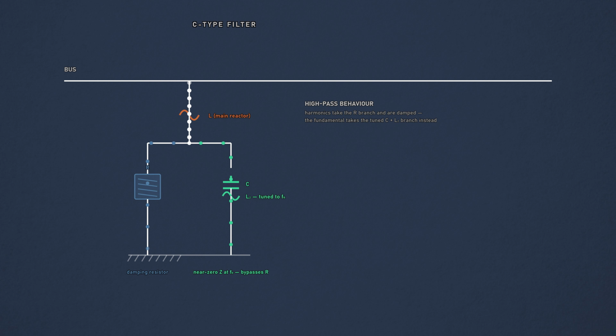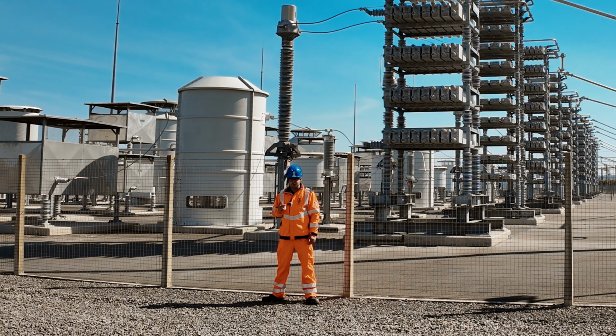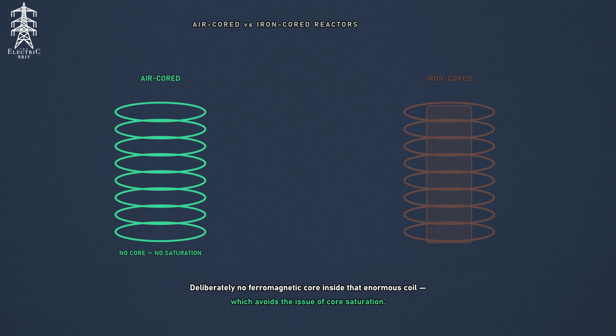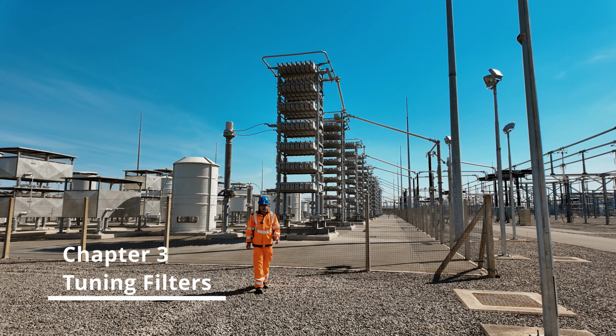And a quick note, reactors are essentially just giant inductors. Big coils of wire, and in this application we typically use an air cored reactor. Unlike the iron cored reactors you'll find elsewhere on the transmission system, there's deliberately no ferromagnetic core inside this enormous coil, which avoids the issue of core saturation when we're loading it full of harmonics. Let's take a second to talk about how we filter before we talk about components.